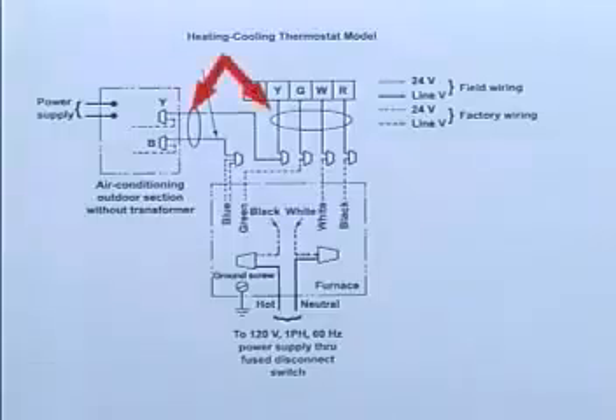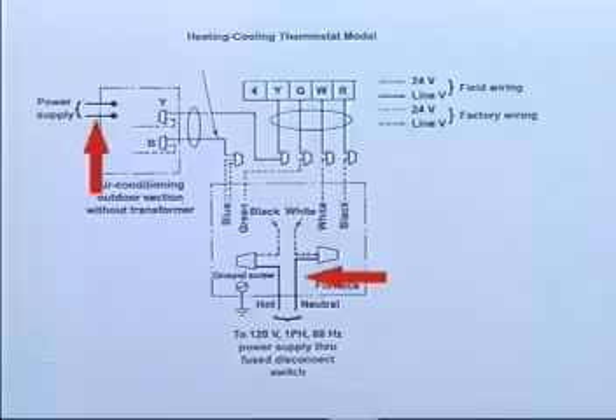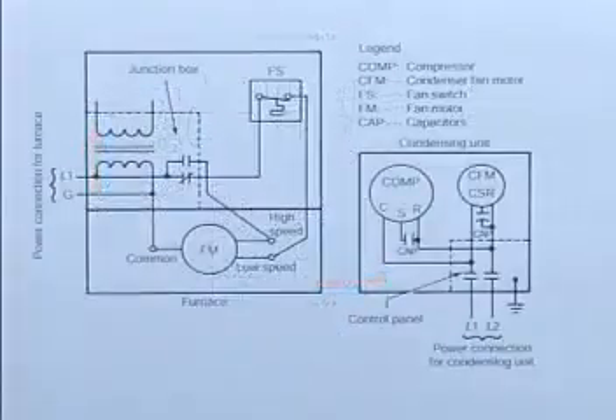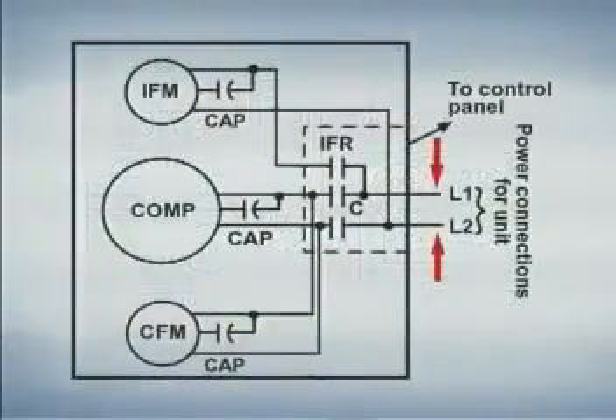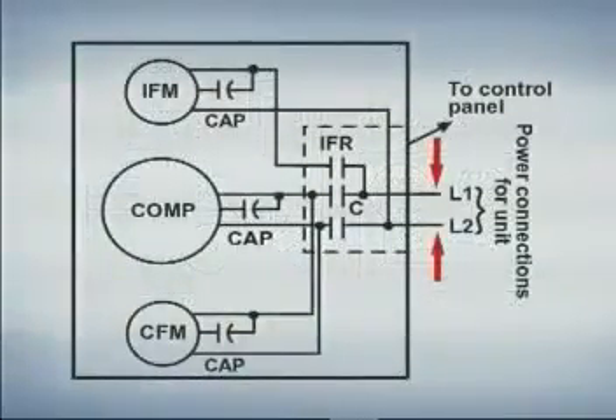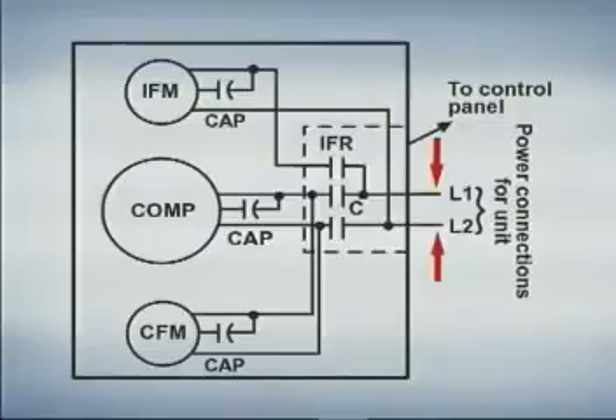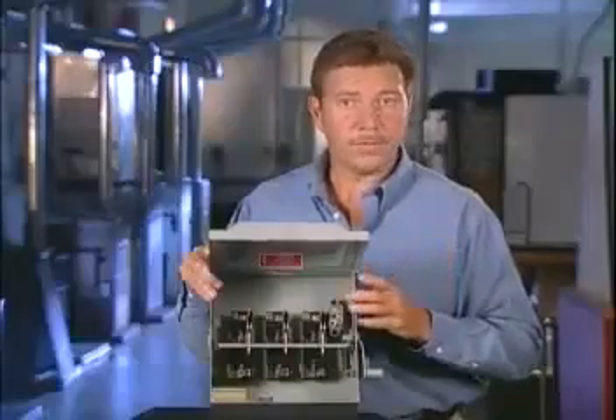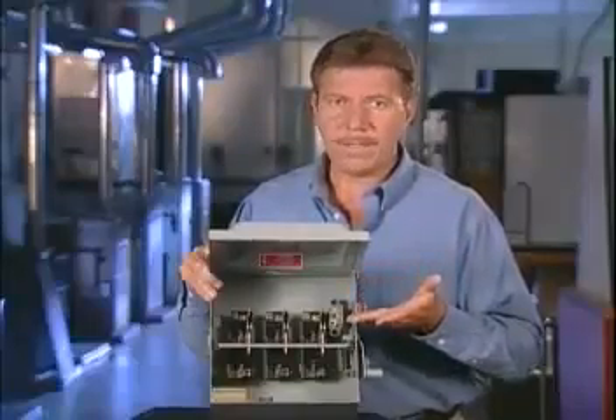Here we can see that the low voltage field wiring is denoted by a thin, solid black line. The line voltage field wiring is denoted by a thicker solid line as shown here. Power must be brought to both the condensing unit as well as the air handler or furnace. The field wiring on packaged systems is typically less complicated because there's only one piece of equipment you need to bring to power.